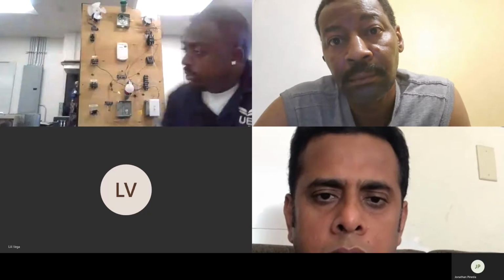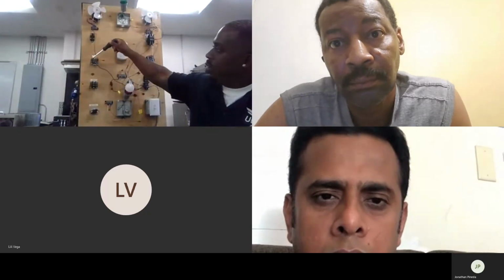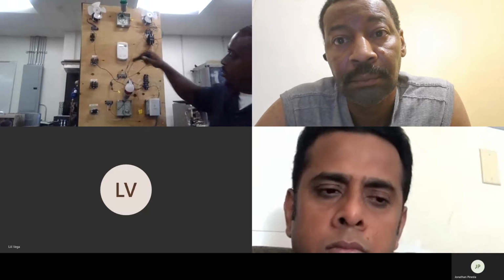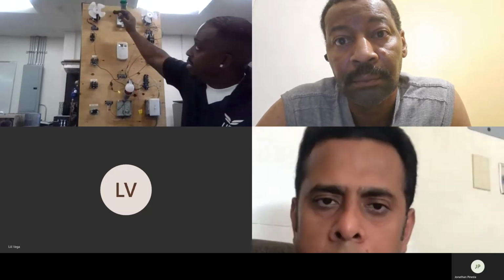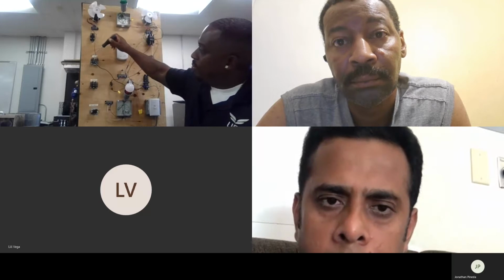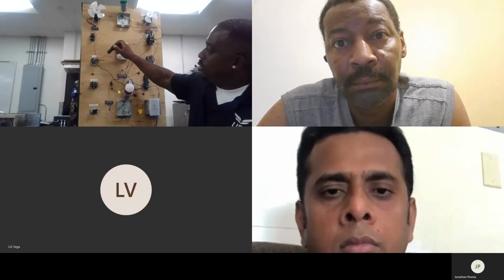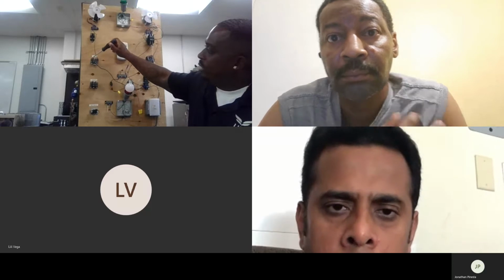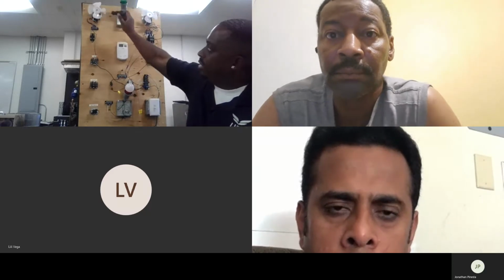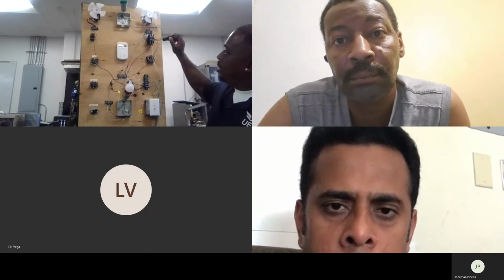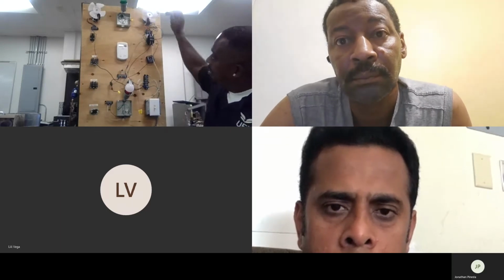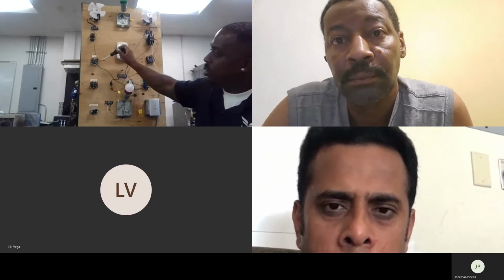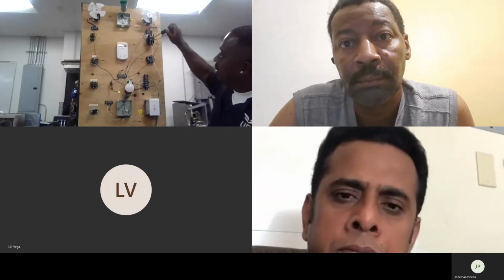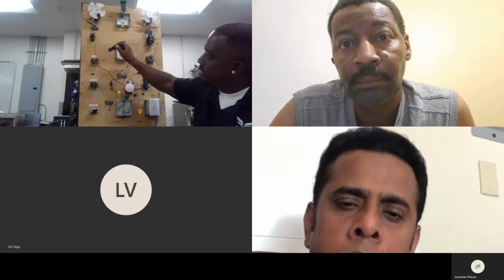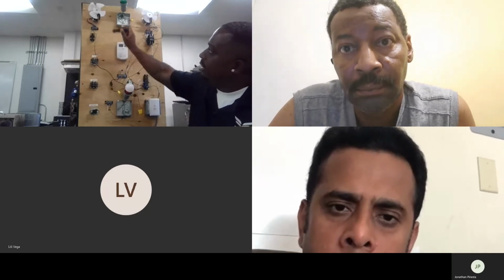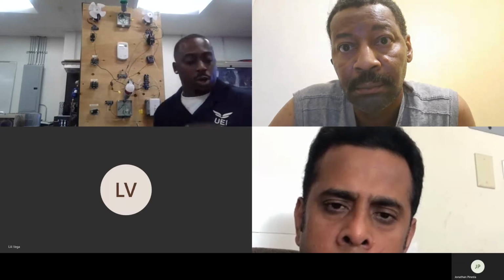All right. So terminal 1 is our power source. It's connected directly to L1. So our 120 volts that's going to power this fan is coming from terminal 1. And once the coil is energized, terminal 1 is going to send that 120 to terminal 3, and boom, the fan's going to start turning. Same way how we have 120 here, and when that closes, that fan's going to go. Same thing over here, except the contacts are internal. Where on these, you can see the contact. This one is internal, but once this coil is energized, power is going to go from here to here, turn that on.